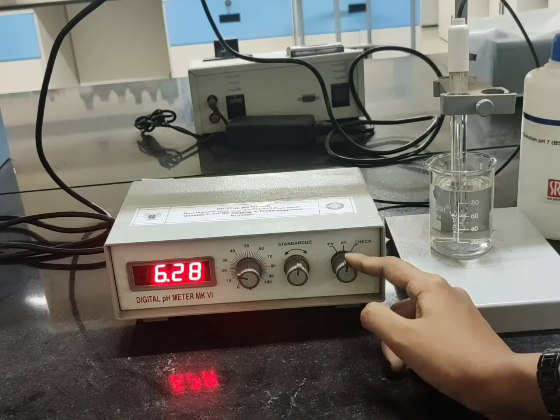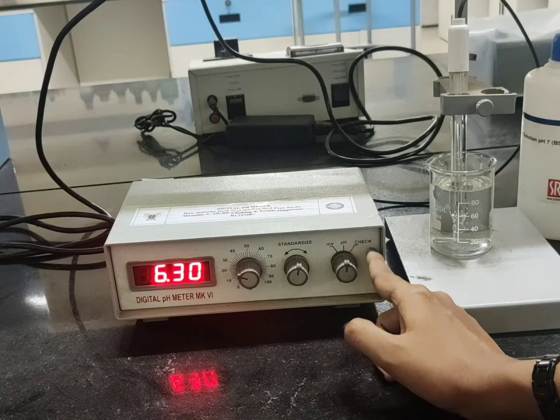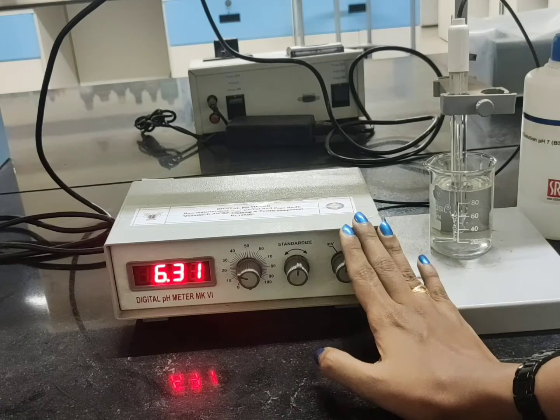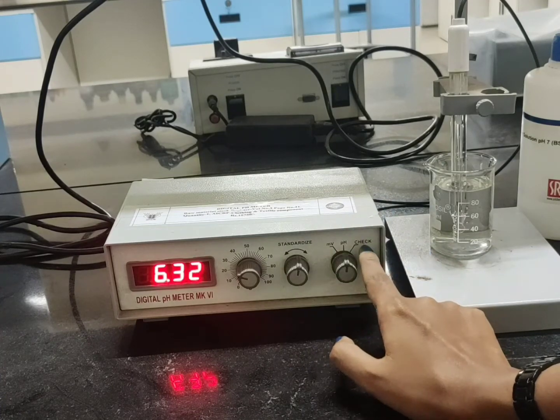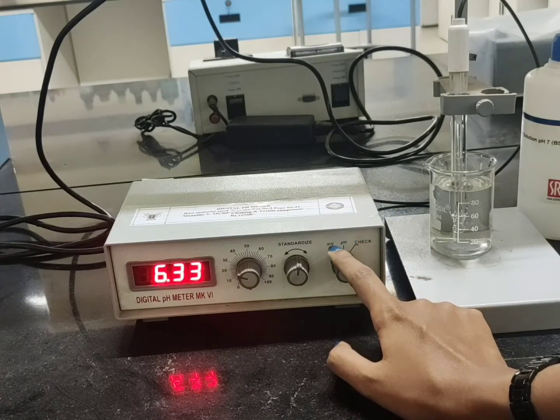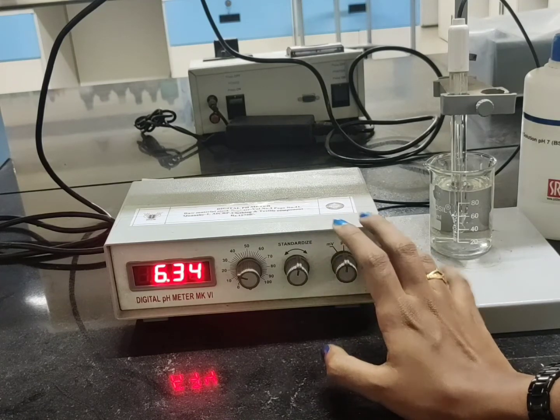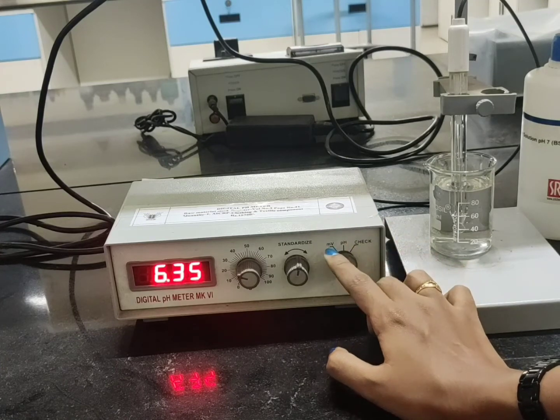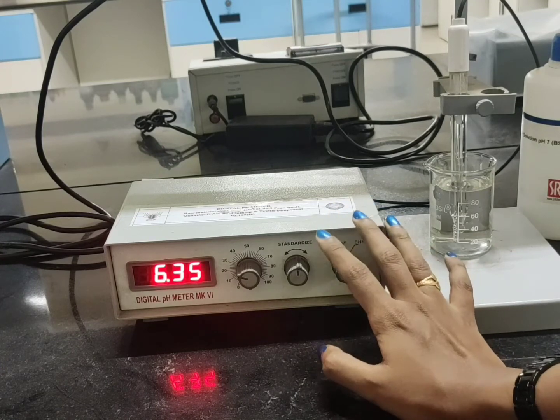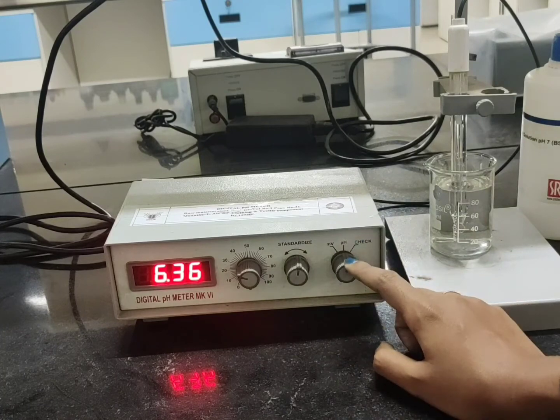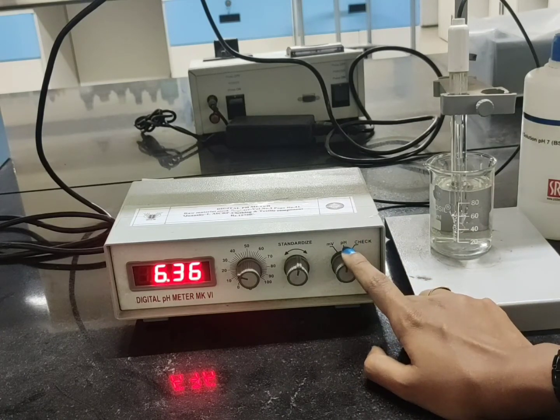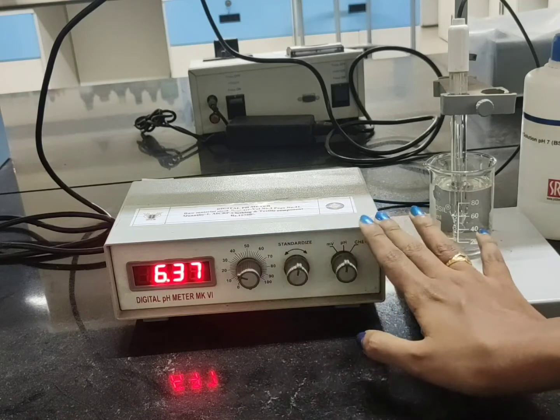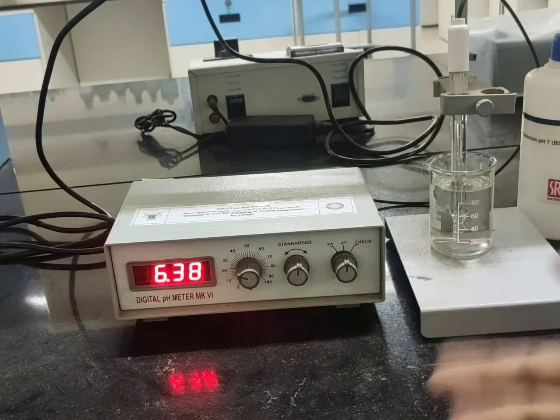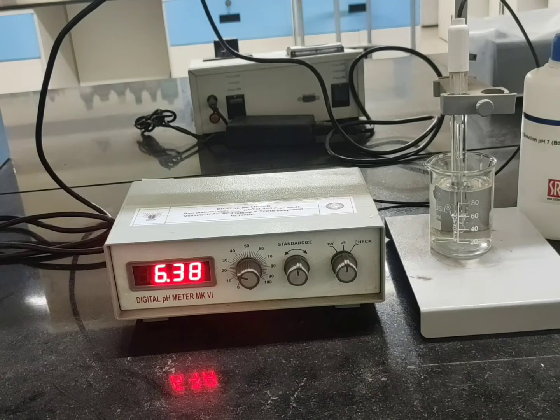Next thing that you see, the third knob is for MV pH check. So there are 3 options being given. In case you are just checking whether the instrument is working properly or not, you can make use of the check. Then one more is MV, which is for the millivolt. So if you are calculating the millivolt of the sample, you can make use of that millivolt, or if you need only the pH, then just keep the knob at the center, which is for pH. Once you do that, your instrument will be ready to go. You can just calibrate the instrument and take the readings.